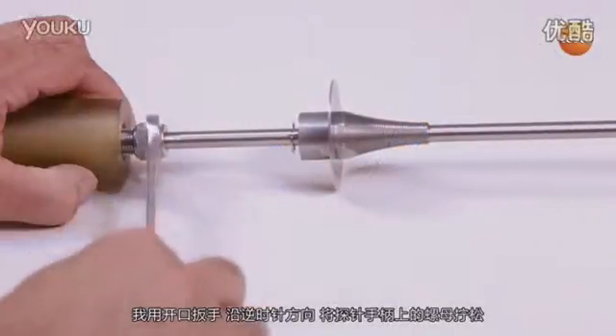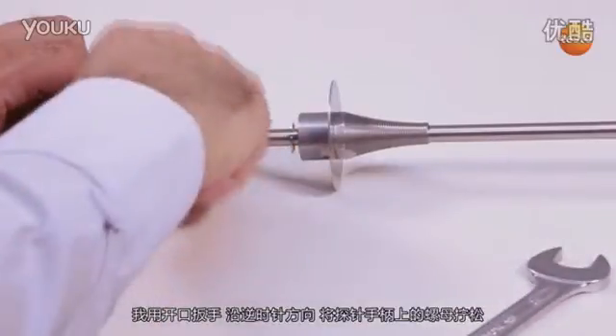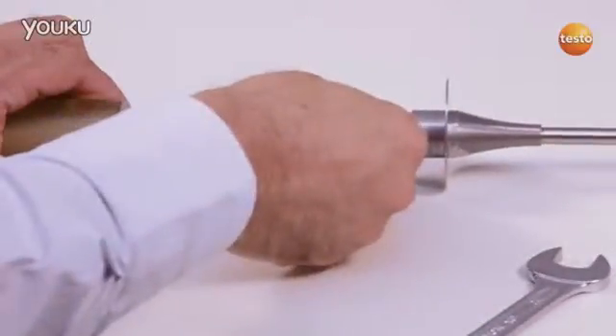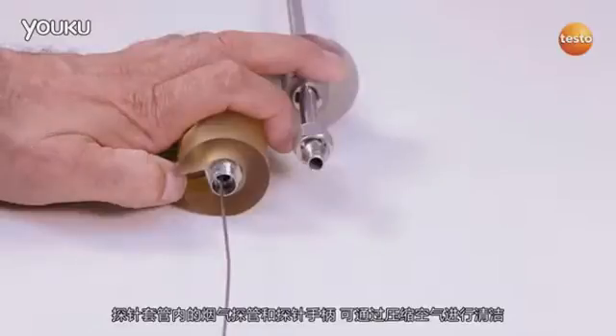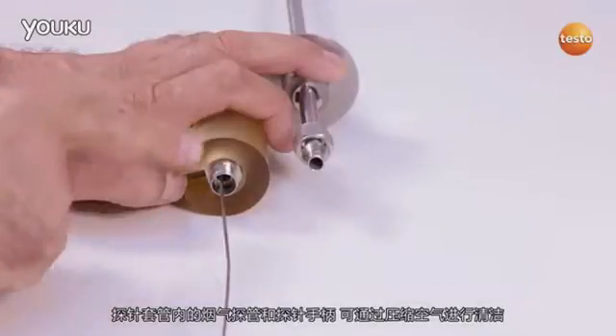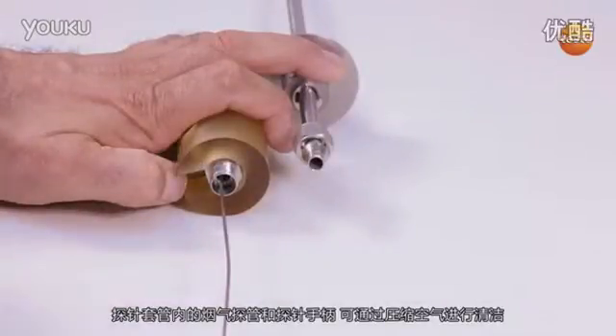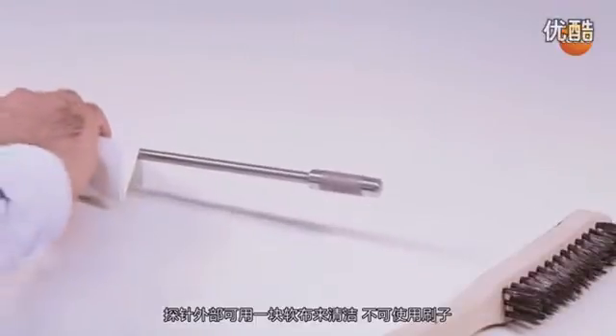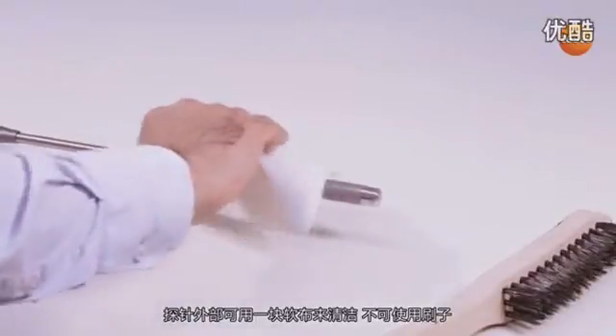I use an open-end wrench to loosen the screw ring on the probe handle anti-clockwise. The flue gas ducts in the probe shaft and the probe handle can be cleaned out using compressed air. External cleaning is done with a cloth. Brushes should not be used.